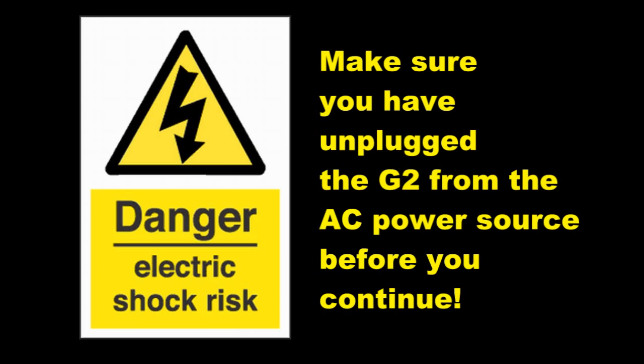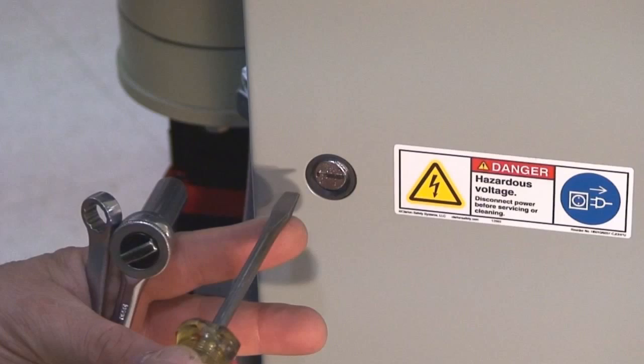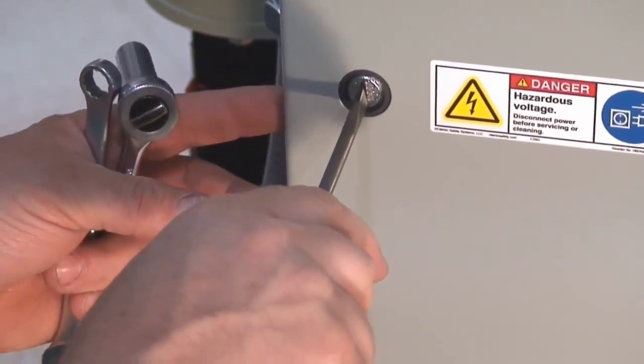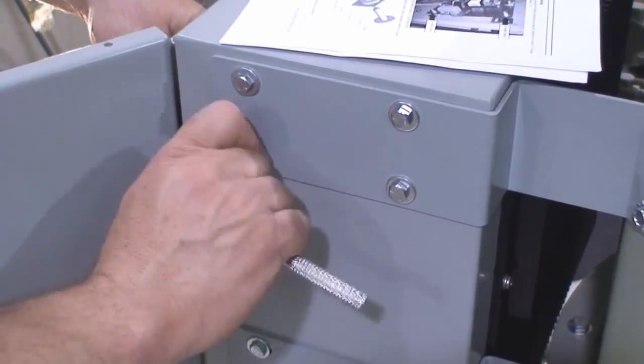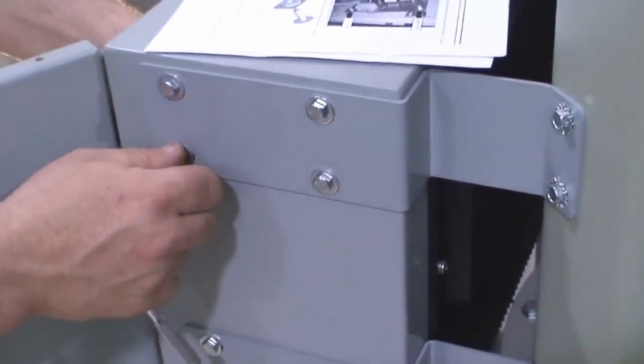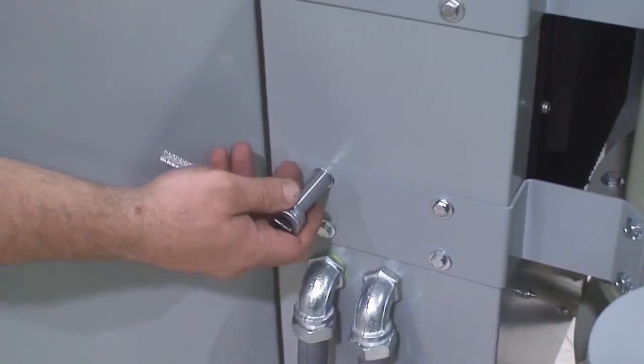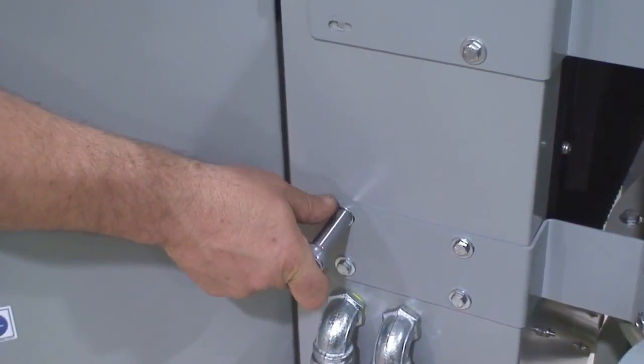Now install the power supply. If you haven't unplugged the G2 from the AC power source by now, please do so right now before you continue. Use a screwdriver to open the rear electronics enclosure. Use a socket to remove the lower bolt from the top mounting bracket and remove the upper bolt from the bottom mounting bracket. Save the washers, you'll use these again.